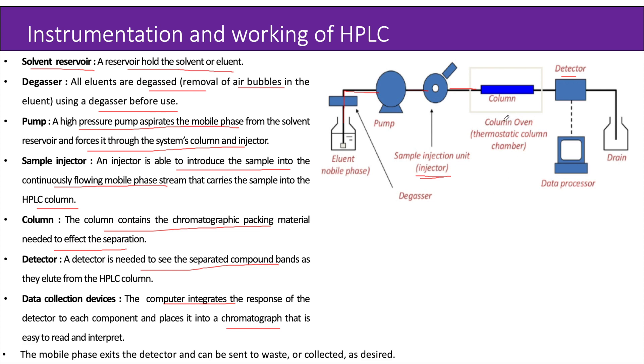Now let us see the working of HPLC. A reservoir holds the solvent, i.e., the mobile phase. It is degassed before entering the column. A high pressure pump — that is, the solvent delivery system or solvent manager — is used to generate a specified flow rate of mobile phase. An injector introduces or injects the sample into the continuously flowing mobile phase stream, which carries the sample into the HPLC column. The column contains the chromatographic packing material, i.e., the stationary phase, needed to effect the separation. A detector sees the separated compound bands as they elute from the HPLC column, and the mobile phase exits the detector and can be sent to waste or collected as desired.